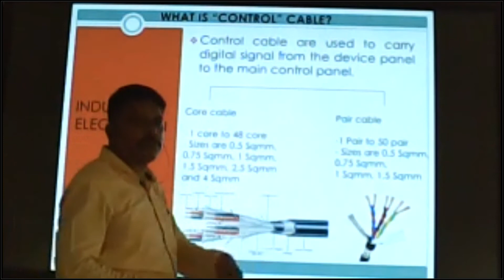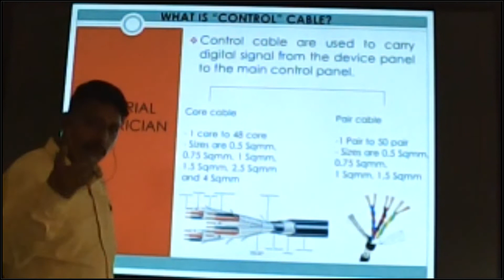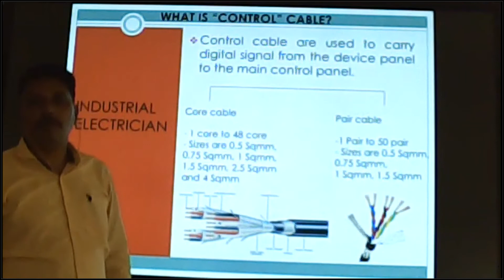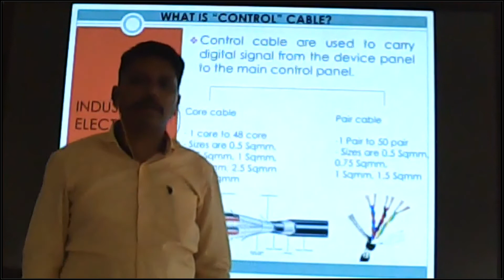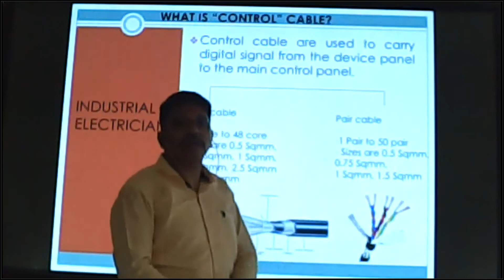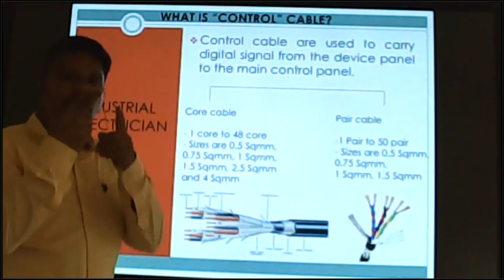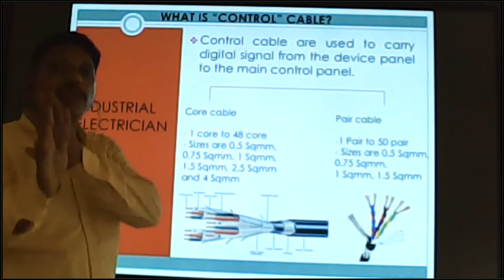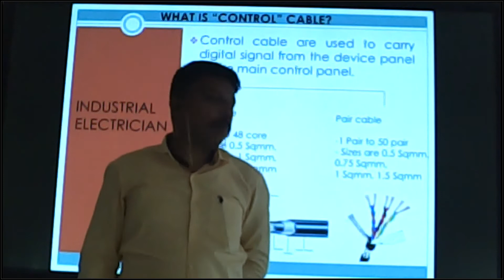There are two types of control cable: core type and pair type. Core type is available from 1 core to 48 core: 1 core, 2 core, 3 core, up to 48. Pair cable comes from 1 pair to 50 pair. Pair means two wires twisted together. Suppose this is a 3 pair cable; it has 6 wires. 2 wires is 1 pair, 4 wires means 2 pair, 6 wires means 3 pair. Clear about this one?